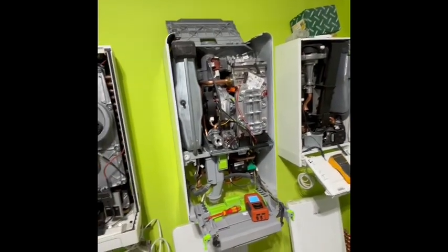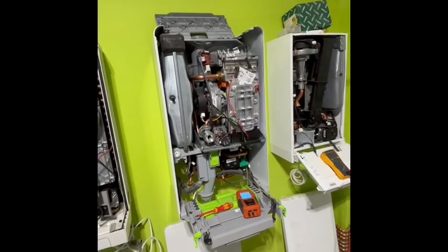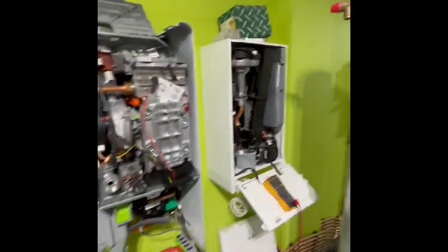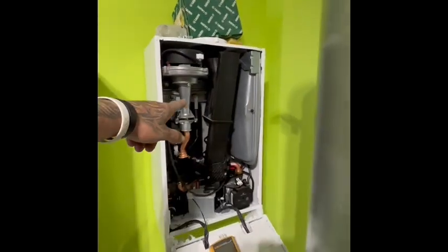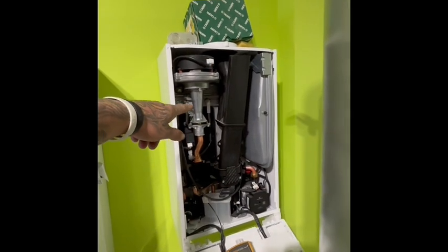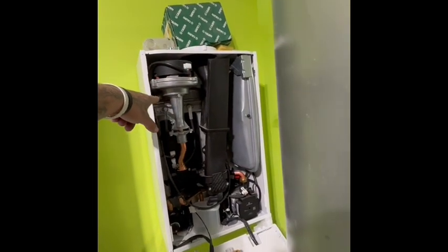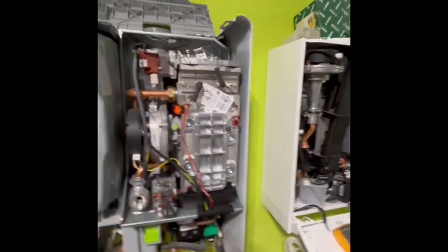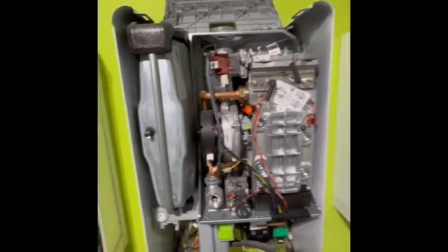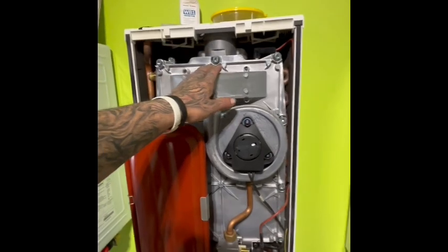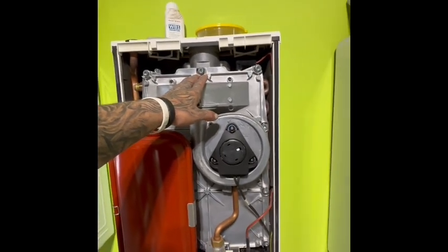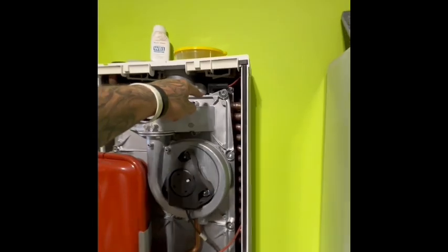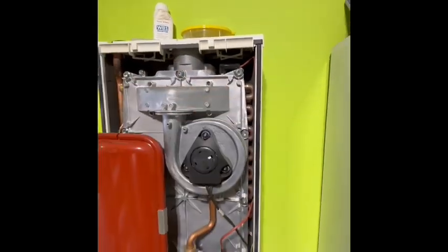But those are the main characteristics of what you're going to need to work through an ignition sequence and find it. Don't be afraid to take that boiler apart. Ideals can come apart without replacing any seals. Just check them, they do stick on the back edges. If it fractures, it's got to be replaced. Worcester Bosch can't take it apart without replacing any seals. Intergas can be taken apart without the seal being replaced, although it should be replaced every 3 years. They tend to go on the top right edge there.